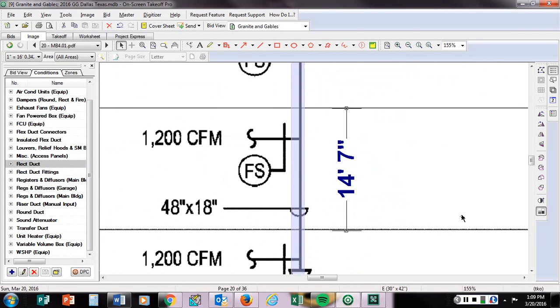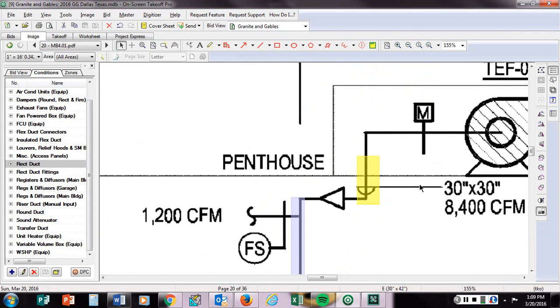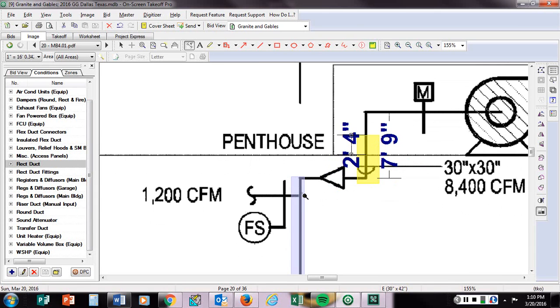So that being said, you see this ductwork coming here. Now here is an exhaust fan with ductwork going up. Not everyone has seen projects get installed, but if I go right to here, that's showing like a 5-foot drop that goes through. It's showing like an 8-foot piece of duct that goes here. That might be a little bit excessive as far as the height from the floor to the fan. It probably is going to be. So what I try to tell you guys to do, because we don't have a good drawing with this, is I'd put this a couple of feet, maybe 3 feet on the high side above the roof here to take care of the vertical drop part of it, and then just run it down to the duct like this. Anything horizontal, do on the other print, and you'll be okay with it.